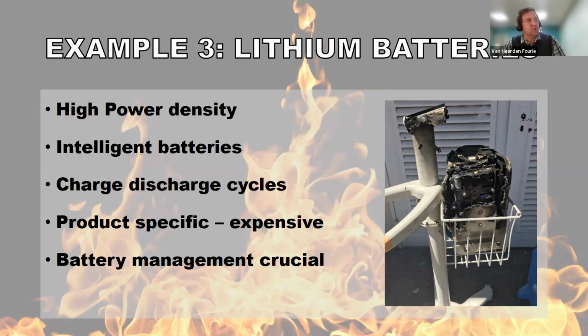With lead acid technology, we were used to using batteries until they failed and replacing them depending on the application. With lithium-ion batteries, it's a different story. By continuing to use them past their cycle, they will still work, but you increase your risk in terms of fire safety. Also, unlike lead acid batteries which are manufactured in bulk and available from several suppliers, lithium-ion batteries come at a premium, so the temptation to keep using them past their specified cycle is high. But we can't afford that risk.